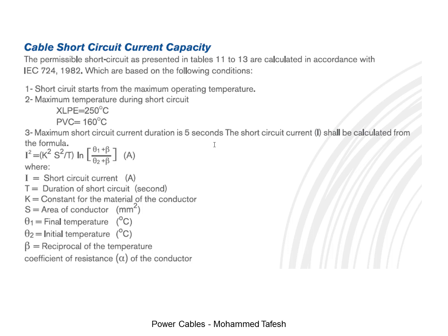The short circuit current I shall be calculated from the formula, where I equals the short circuit current in amperes, T is the duration of short circuit in seconds, K is a constant for the material of the conductor, and S is the area of the conductor in millimeters squared.